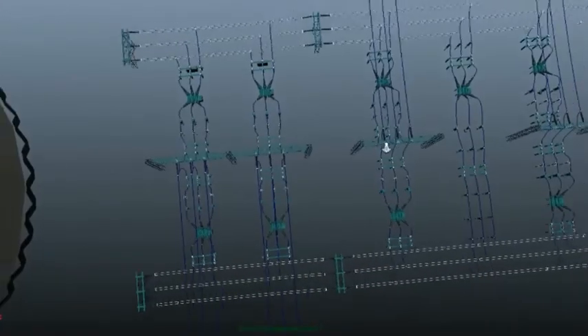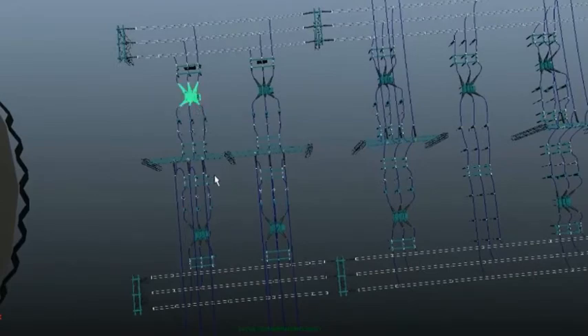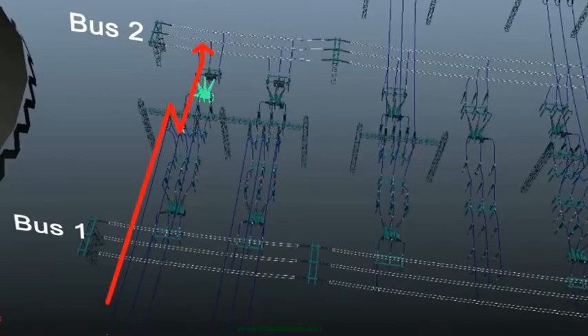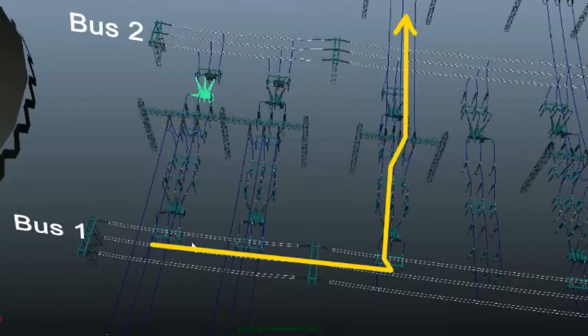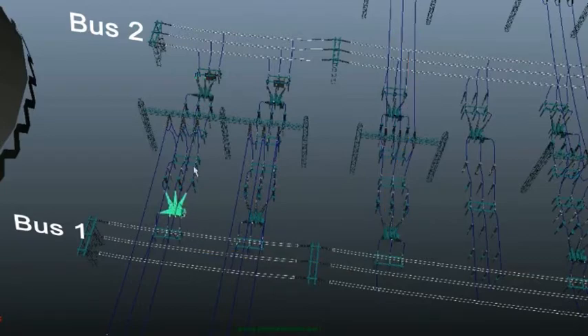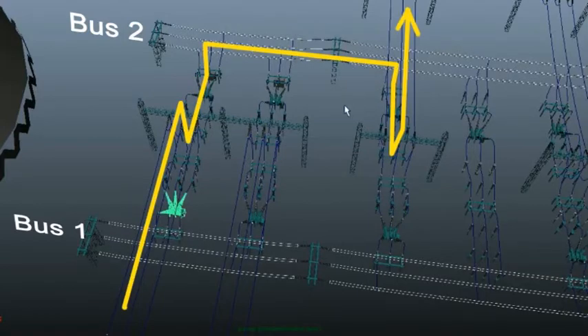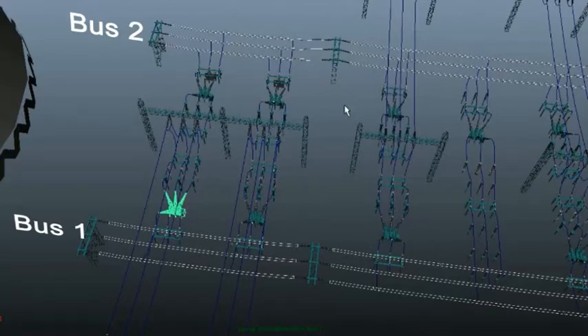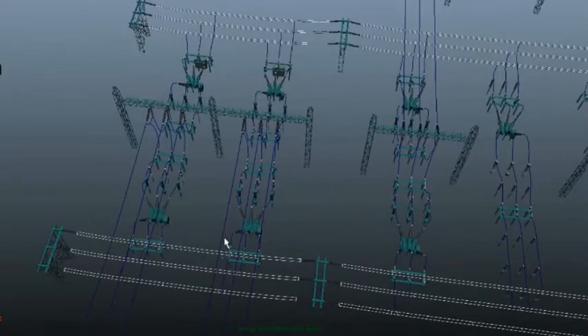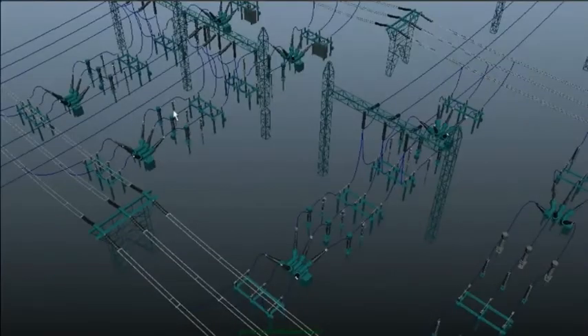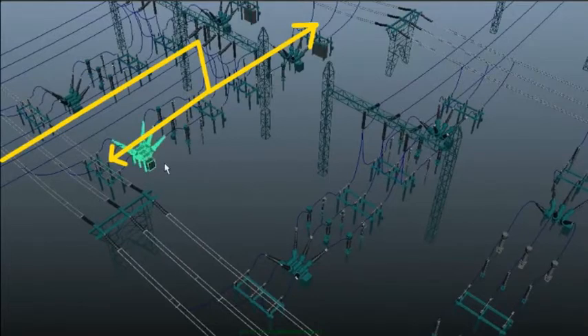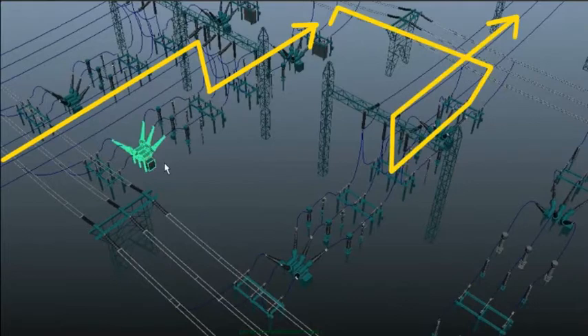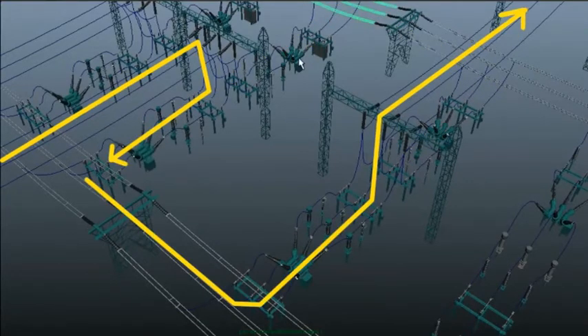Now, what are the advantages of having 2 buses? Let's understand this. Suppose due to some fault, this circuit breaker becomes switched off. The power will not enter into bus 2 and will completely start entering into bus 1, which was partially entering into both the buses. And it will continue further into the transmission line from bus 1. Suppose this breaker gets off, then the power will continue from bus 2, so the continuity will remain. It will never happen that our supply will completely stop. The same thing is applicable in the case of another incoming line, which is coming from the other transformer. Like if this breaker gets off, the power supply will continue from here, and if this one is off, then it will go from here.